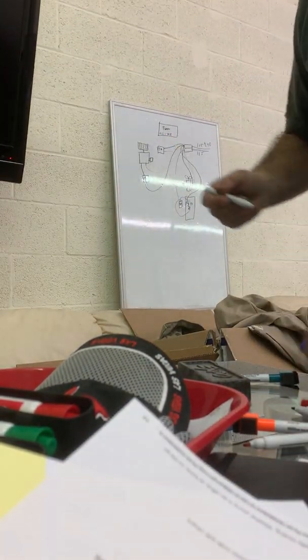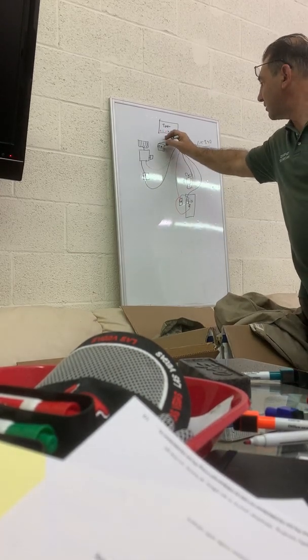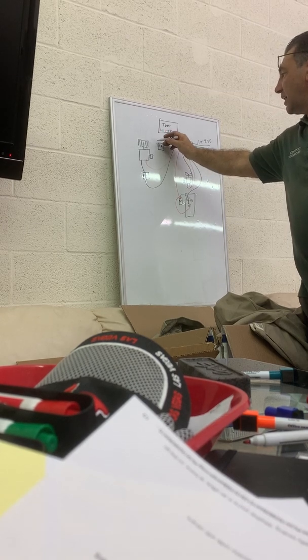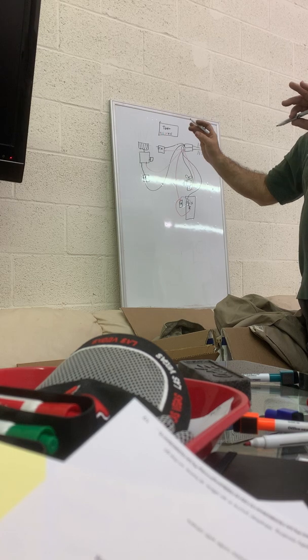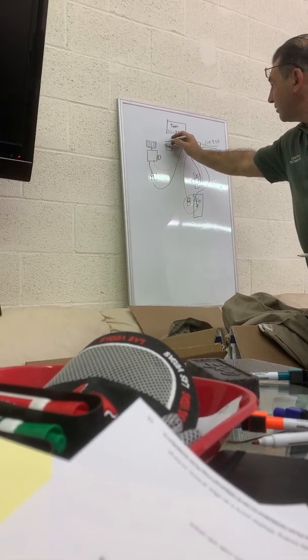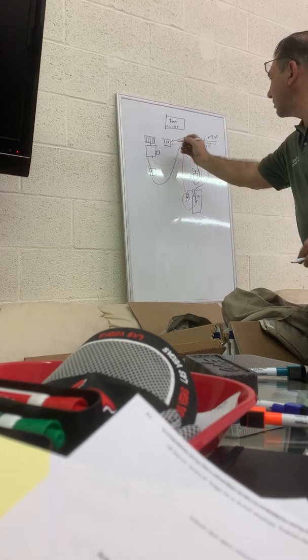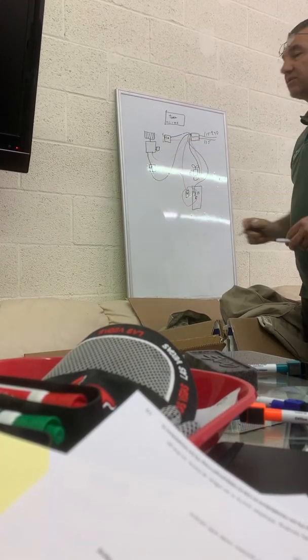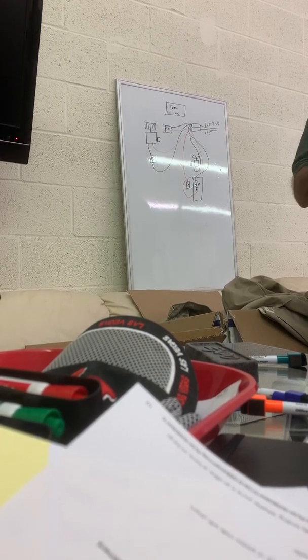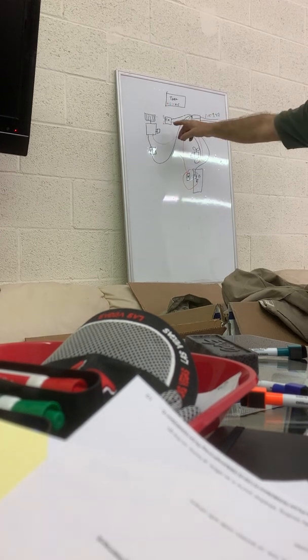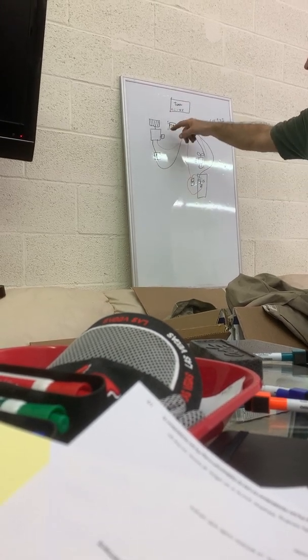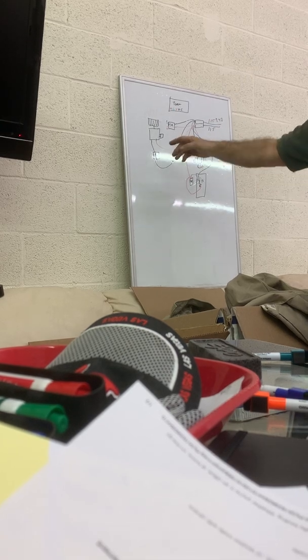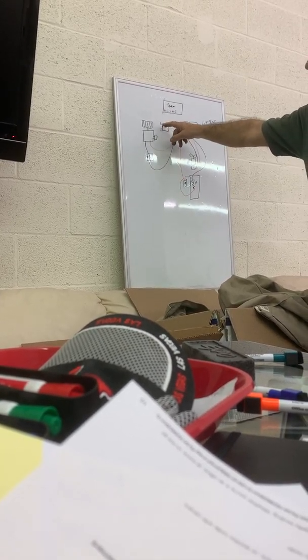The transformer will generate 24 volts, two wires. One we'll dedicate as common - we'll decide one side is common. The other side is R, it's red. That's why when you open the unit, most of the time you see a red wire - I'm talking about low voltage. It's 24 volts live, and a blue or black wire will be common.